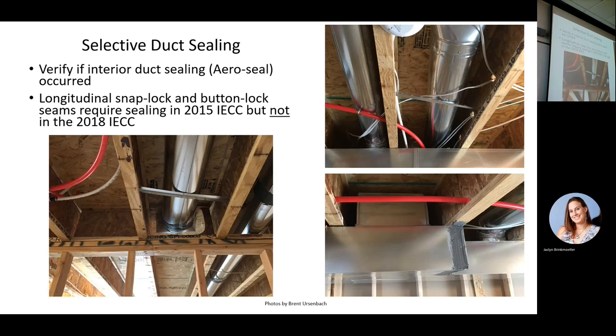Selective duct sealing. These are all the same house. They didn't seal this, they didn't seal this, they did seal this, and they did seal that. However, some of these, it looks like they've sealed what looks like big leaks and not sealed others. And guess why? Because they did spray duct seal. Has anybody seen that, where they open up the duct and they spray a mist in there, they pressurize the duct, and it seals internally? They block it off so you don't get it on the coil and you don't get it in the furnace. But they pressurize and spray a latex sealer in there, and it seals the duct. And in fact, they call it Aero... I'm trying to remember. AeroSeal.